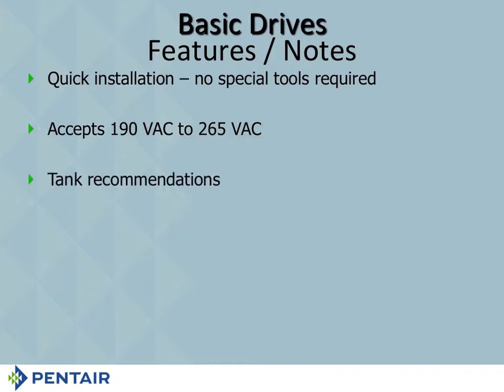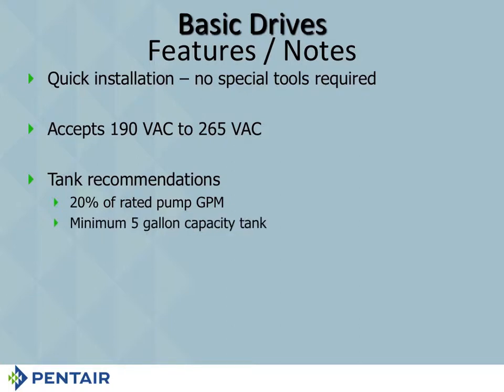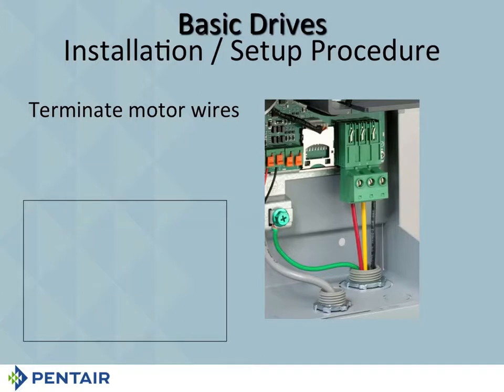Now, tank recommendations: 20% of the rated flow of the pump or a minimum of 5 gallons. Now, 20% would mean that if I was running a 20-gallon-per-minute pump, that would be a 4-gallon tank, so I'd want this minimum tank. Now, if I'm running a 50-gallon-per-minute pump, that's going to be a 10-gallon tank, which means I'll probably wind up using a 19. Let's talk about your wires here.